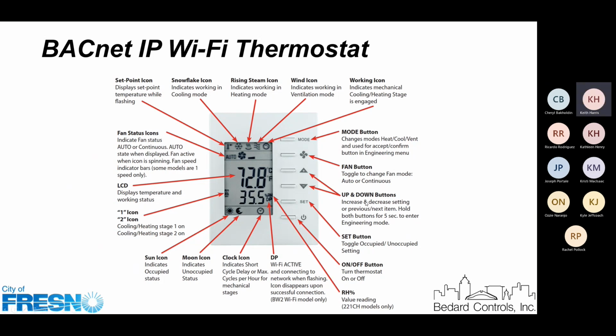The two buttons that are probably the most important are the up and down buttons. Those allow you to change the temperature up or down as low as the prescribed set points for that type of activity. So in cooling, you can go down to 74 degrees, and in heating, you can go up to 68 degrees. The set button is also important because that button, if you should come in when the space is unoccupied and you want it to start to heat or cool because you're going to be there for a while, you hit the set button and it'll change it from unoccupied to occupied.